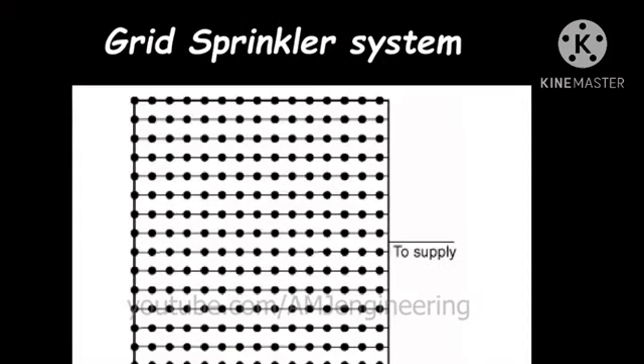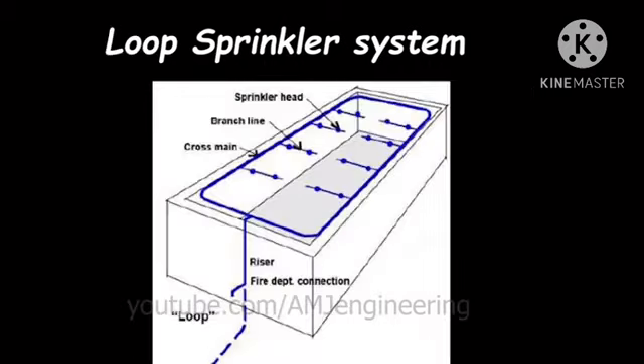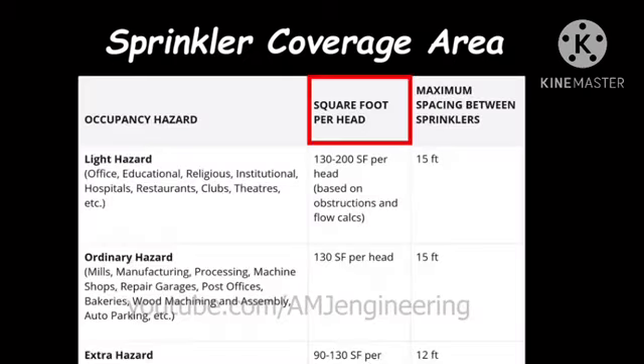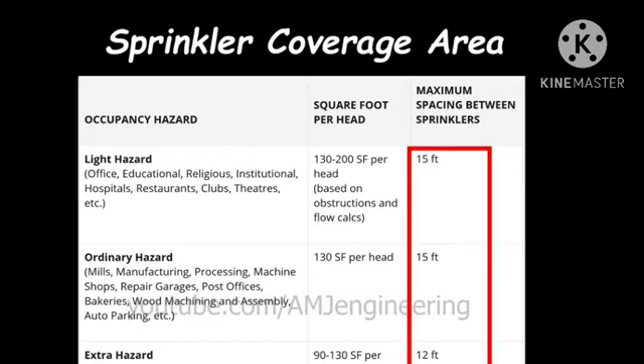Grid sprinkler system. A sprinkler system in which parallel cross mains are connected by multiple branch lines. Looped sprinkler system. A sprinkler system in which multiple cross mains are tied together so as to provide two paths for water to flow to an operating sprinkler, and branch lines are not tied together. The maximum area of coverage per sprinkler head depends on hazard classification and sprinkler mounting orientation, that is, sidewall or overhead. Sprinkler head spacing. The table below shows sprinkler spacing requirements based on NFPA 13.